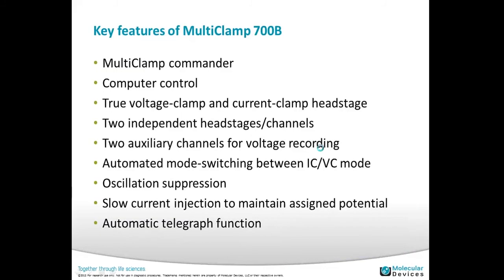There's a lot of good features about 700B. I'm not going to talk about all of them, but I'll highlight some. For example, this headstage has two independent headstages and two auxiliary channels for additional field potential recording, plus automated mode switching between current clamp and voltage clamp mode, oscillation suppression, and slow current injection.